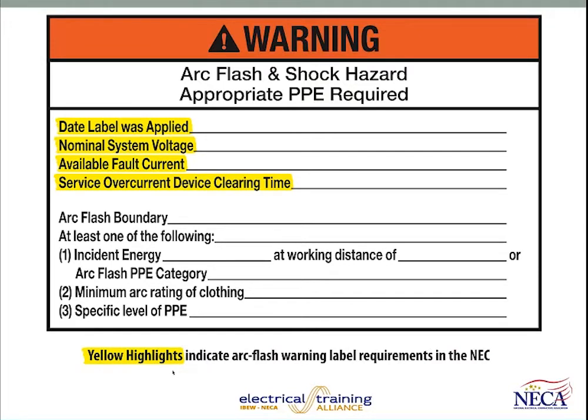The expanded requirements in the 2017 are highlighted. The date the label was applied, nominal system voltage, available fault current, and service overcurrent device clearing time. And those are all factors that are used when you're applying the table method of establishing incident energy levels and levels of PPE that must be worn in a given work practice.